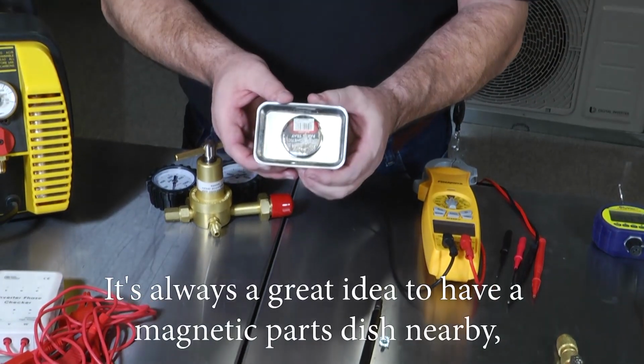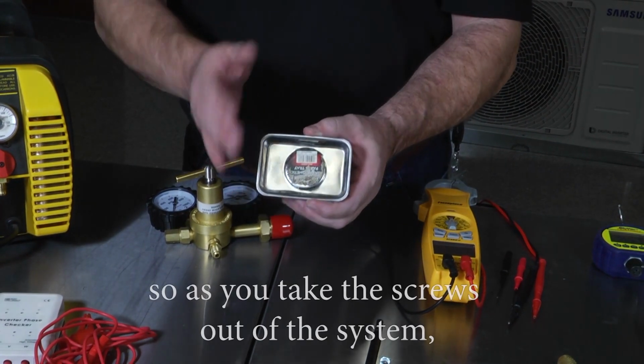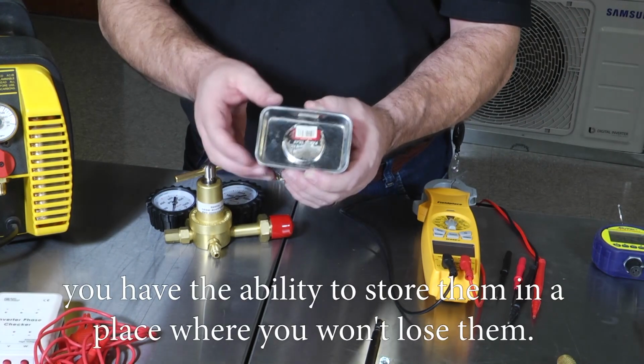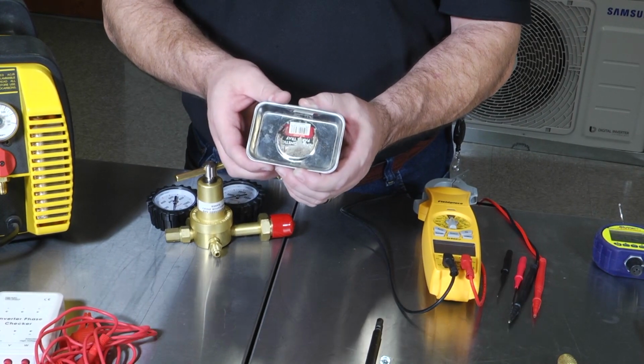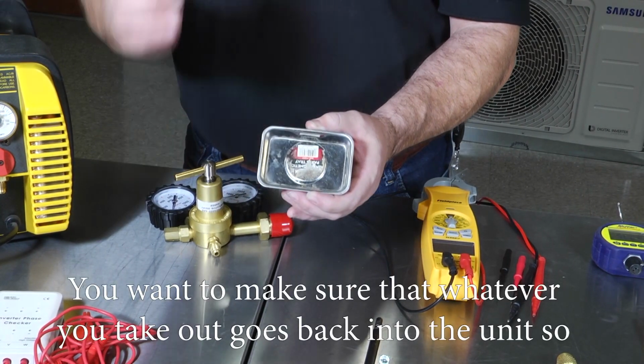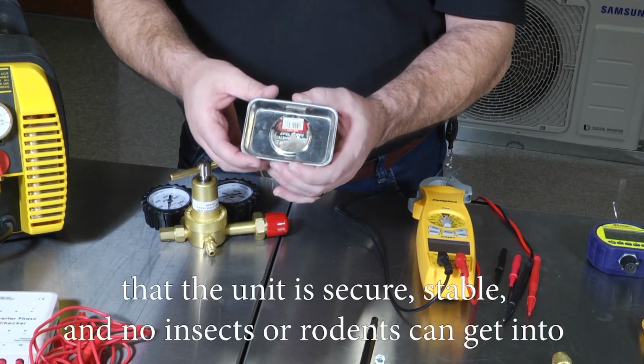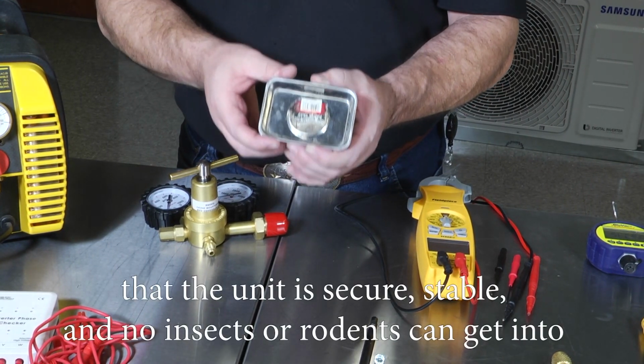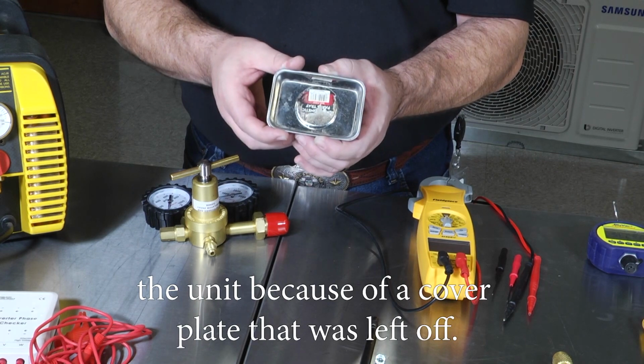It's always a great idea to have a magnetic parts dish nearby, so as you take the screws out of the system, you have the ability to store them in a place where you won't lose them. You want to make sure whatever you take out goes back into the unit so that the unit's secure, stable, and no insects or rodents can get into the unit because of a cover plate that was left off.